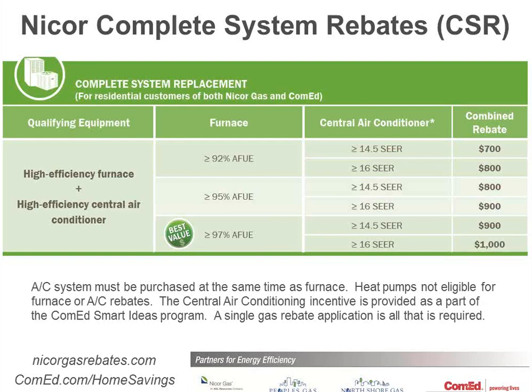The SEER ratings have to be the SEER rating that is represented on the AHRI website for the combined rating. Combined rating means the air conditioner with a specific model number of evaporator with a specific model number of furnace. Those 3 combined together get a SEER rating, and if you change to a different evaporator or to a different furnace, you will get a different SEER rating for that air conditioner. So it's not the SEER rating in the marketing literature, it's the SEER rating that is listed on the AHRI website for that specific combination of 3 widgets. So just keep that in mind.